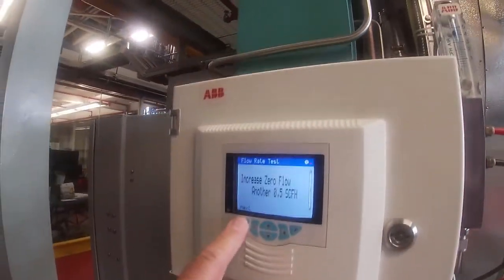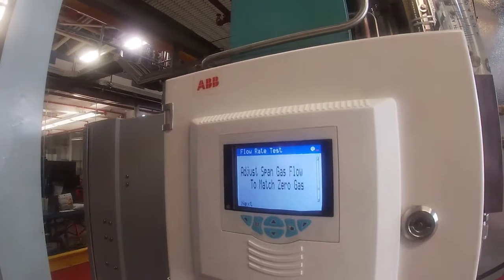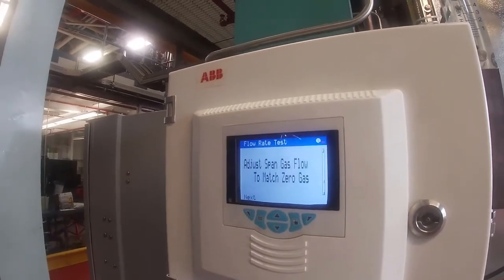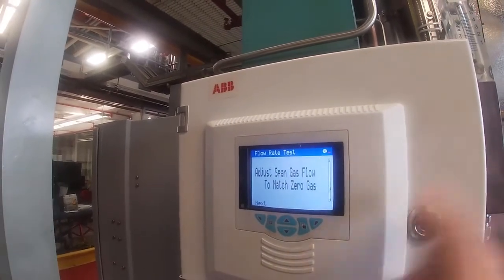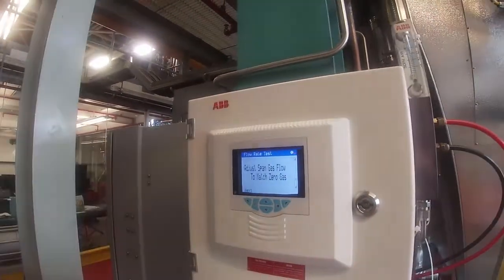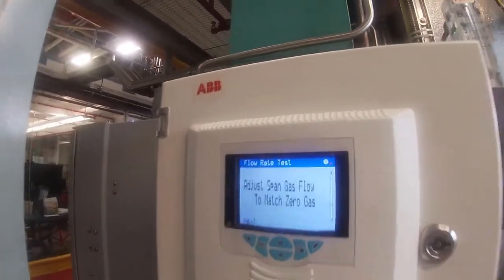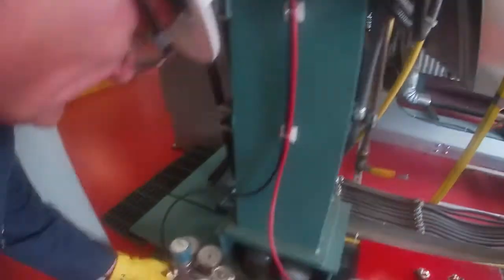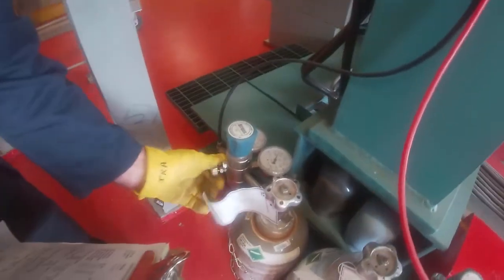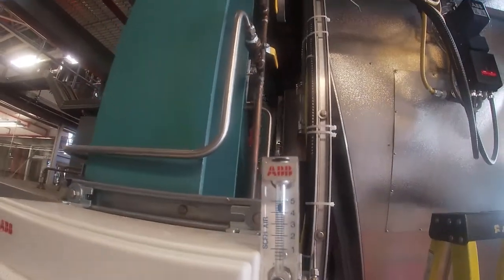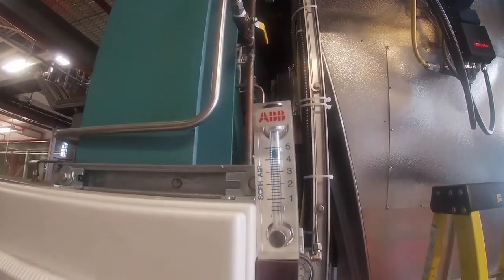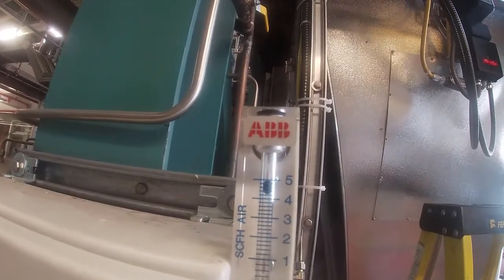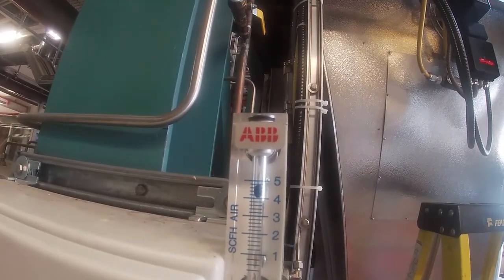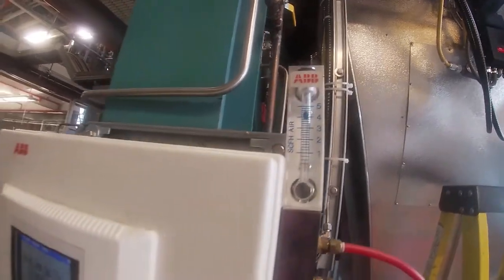Okay, so now we hit the next key. It says adjust the span gas, so it's actually opened the solenoid valve for span gas in here to match the zero gas. So I'm going to open up my drop valve, that valve, and adjust the regulator till I get 4.5. Wow, I'm very close. That's pretty close to 4.5.